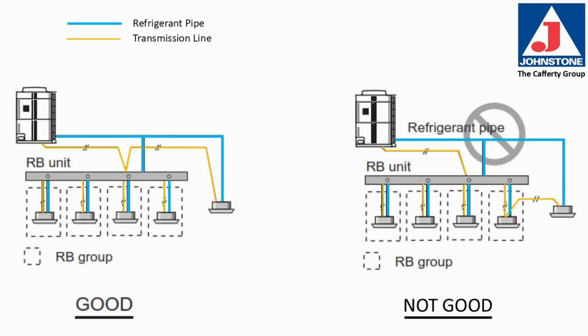Here's another example of a multi-port RB box. Each indoor unit is in its own group and connected individually to the port it's piped and wired to. The example on the right shows that the farthest two right units are connected with the communication between them. The unit on the far right needs to be wired to the main daisy chain so it can communicate individually and not through the same port as the fourth RB unit connection.